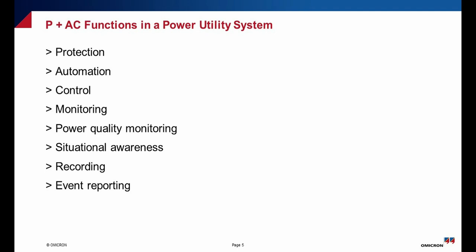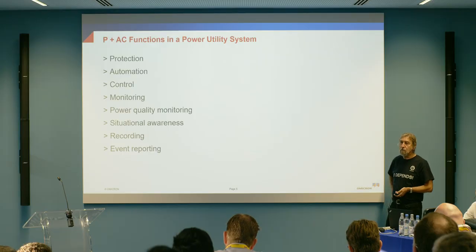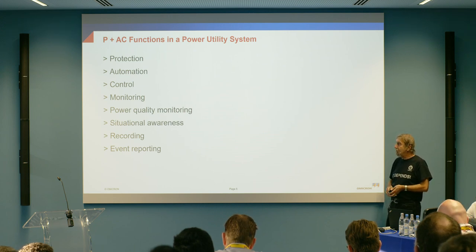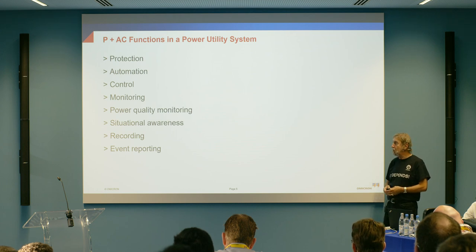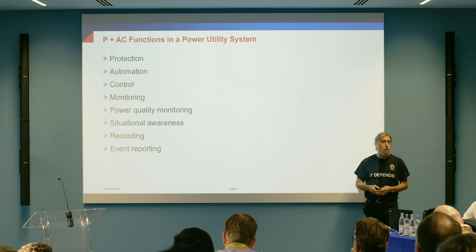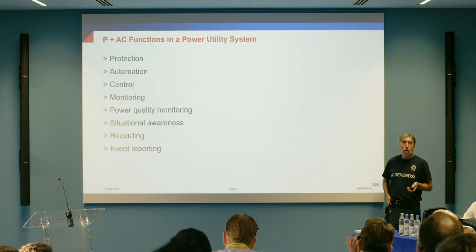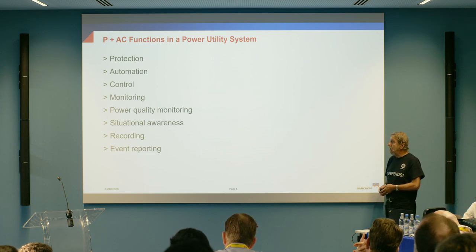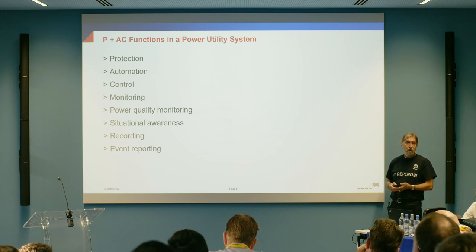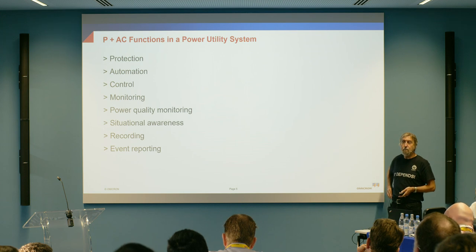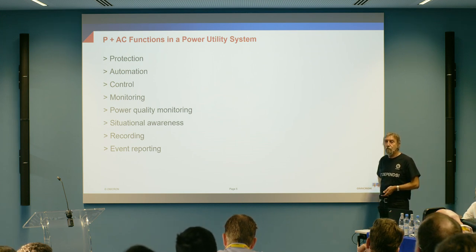When we think about the P plus AC functions in a power utility system, they are actually overlapping functions. It is becoming more and more difficult to separate one from the other, because in order to implement a protection function you have to have monitoring of the state of the system, you have to implement certain automation functions in order to restore the state of the grid after an event, you have to have the ability to control the system locally, remotely, at the system level and at the distribution level. You also need to monitor the quality of the power, which is becoming very critical because we have computer-driven loads that are sensitive to voltage variations.